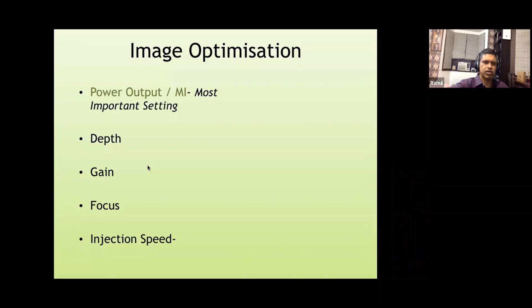So our instrument settings we should be familiar with while utilizing contrast. Although just by choosing the preset LV opacification on our instruments, most of the presetting will be done. But generally, the basic ultrasound principles should always be kept in mind. Power output or mechanical index, we should know where the buttons are. We can reduce the mechanical index. It's one of the most important settings, as I mentioned. Minimum depth required for optimum imaging, gain settings should be optimal, focus should be on the area of interest, and in terms of contrast, also the injection speed is very important. In case we are doing bolus injection, which most of us are doing for LV opacification, bolus is the easiest form of injection. So injection speed is also an important factor. So these are a few examples.